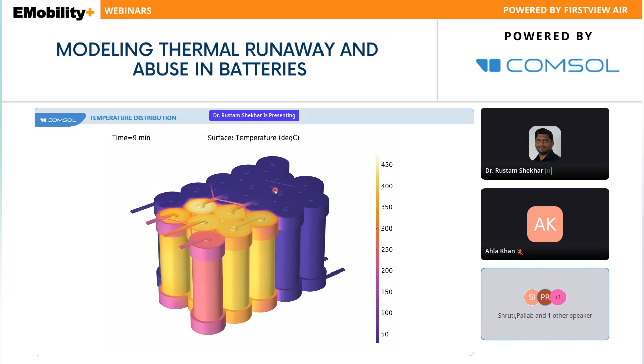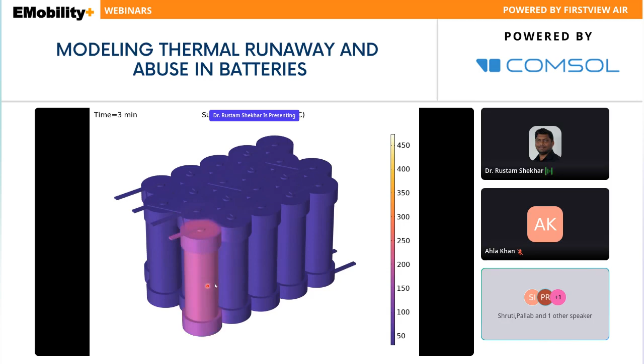Now, if you want to do something to prevent this, that can also be done in this kind of scenario. We can have some kind of wrapping around it, using phase change materials, filler material, or decoupling the cell when it gives an alarm of failure. So all those strategies can be taken, and you can design your thermal runaway mitigation scenario.